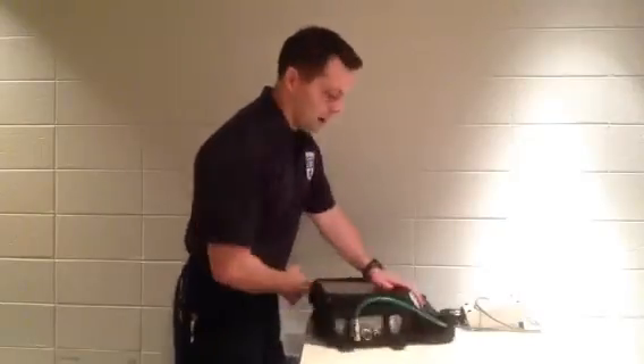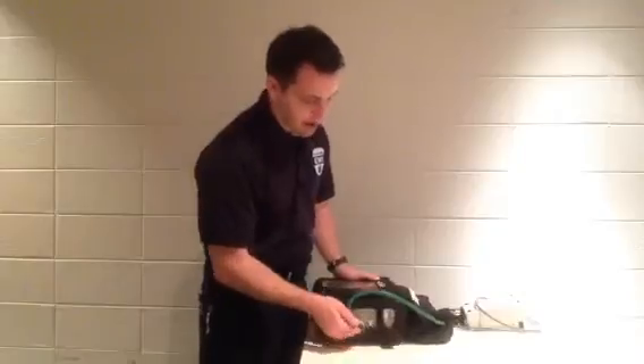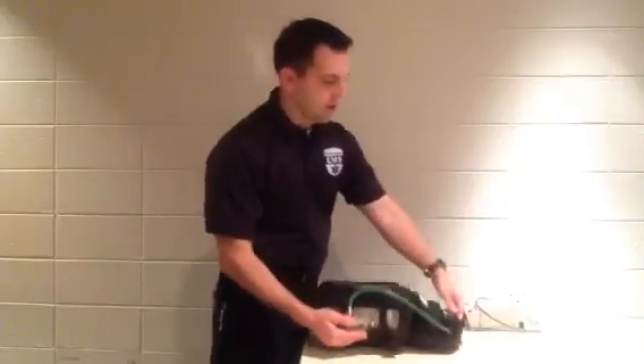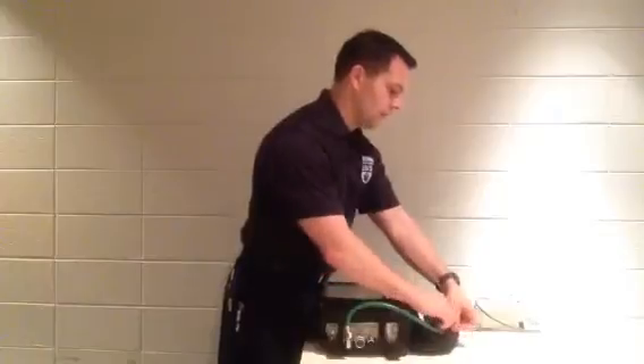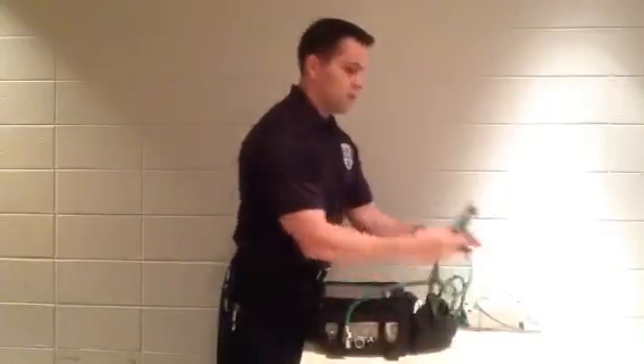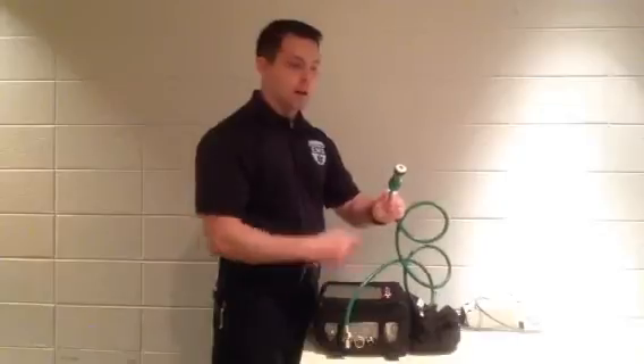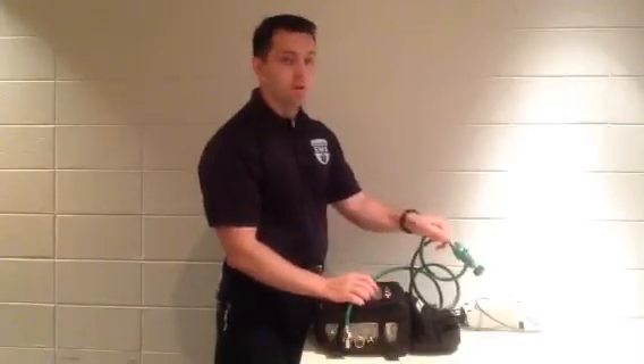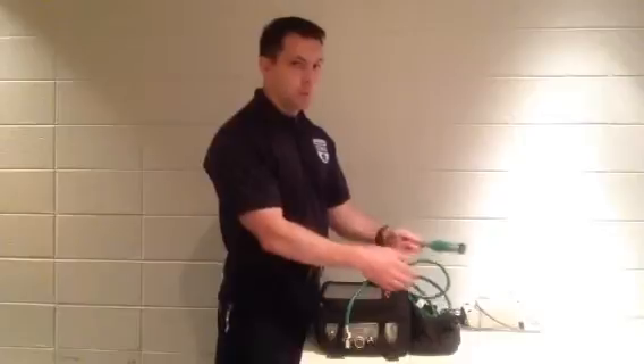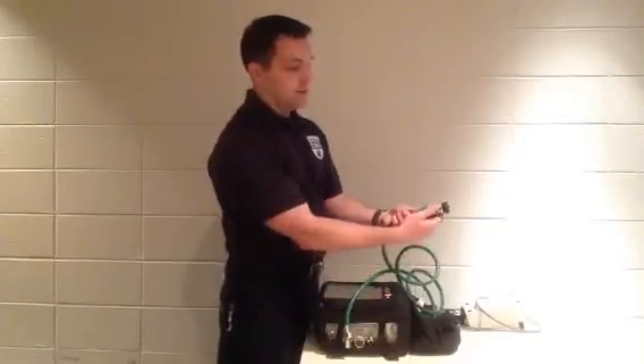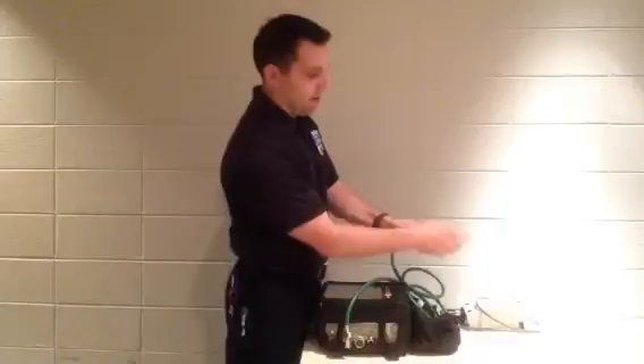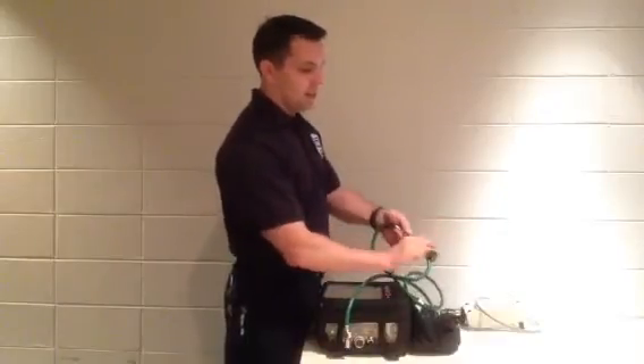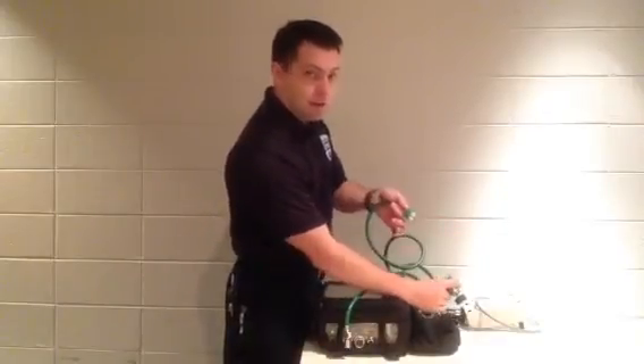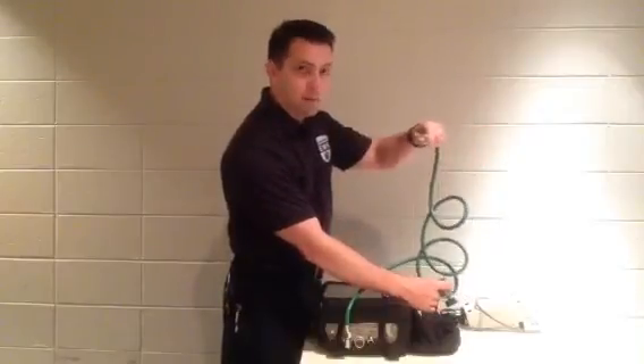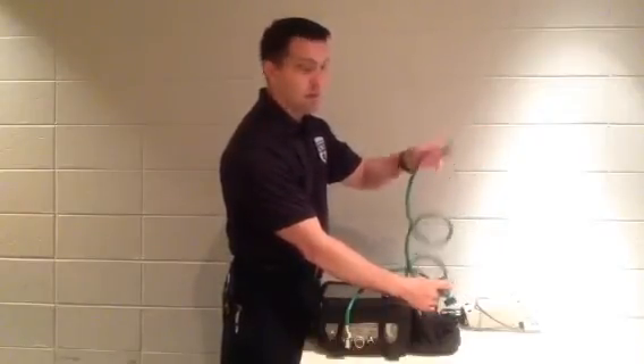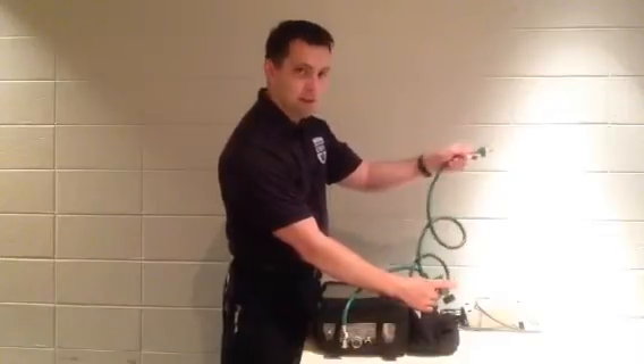Just to get started, here's where all of your inputs and outputs are. You have your 50 psi line, and that's just stored in its own little pouch. When you take this out, you notice that it has a connector. It has the threaded connector which would go onto the O2 bottle, either in your portable bag or mounted onto the stretcher. It has the quick disconnect feature here that pops that off, and therefore you can be on the bottle, you can disconnect from the bottle and immediately go into the side port of a wall, either at the bedside or more appropriately inside the ambulance.